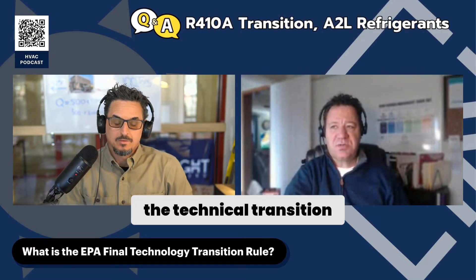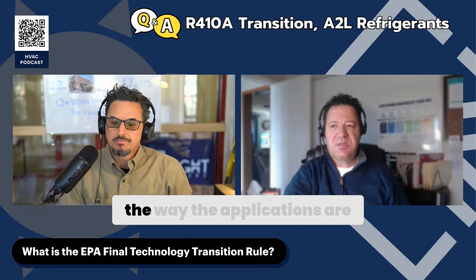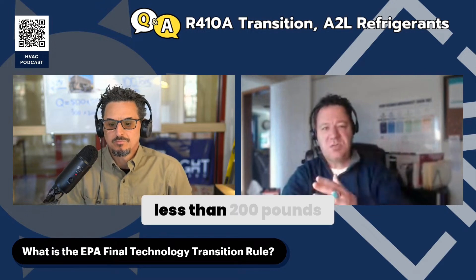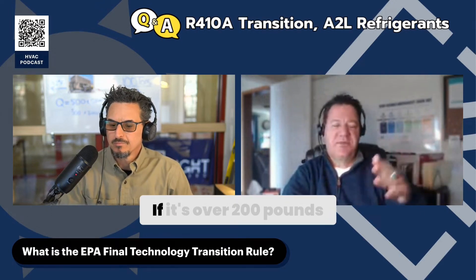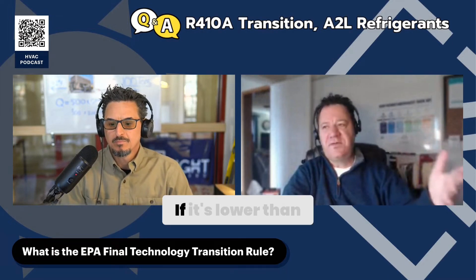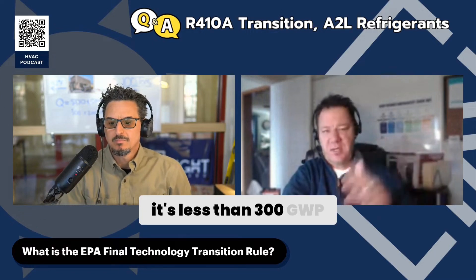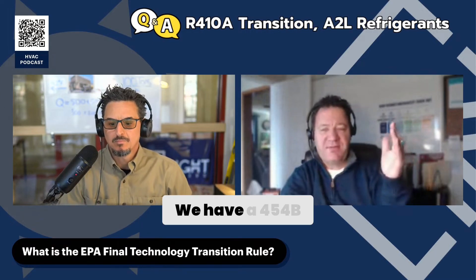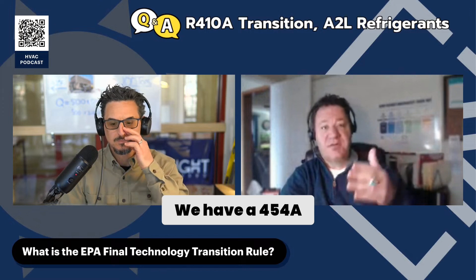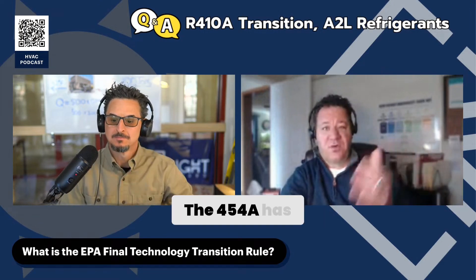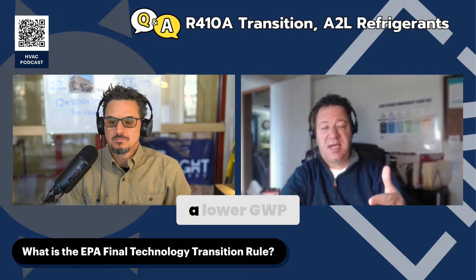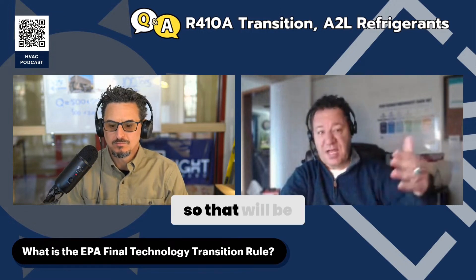The Technology Transition is really about the systems, the applications, how much refrigerant is in the system — whether it's less than 200 pounds or over 200 pounds. That changes things. If it's over 200 pounds of commercial refrigeration, the maximum is 150 GWP. If it's lower than 200 pounds, it's less than 300 GWP. We have 454B for air conditioning at less than 700, and 454A and 454C — 454A has a higher GWP for under 200 pounds, and 454C has a lower GWP for the under-150-pound applications.